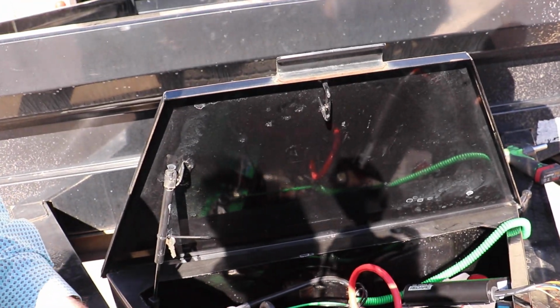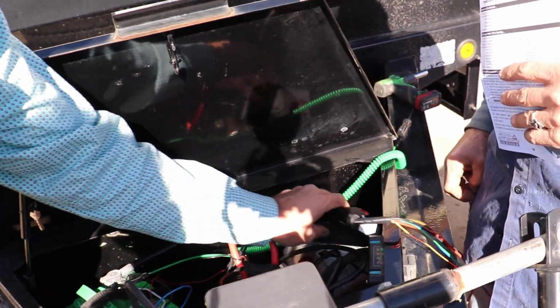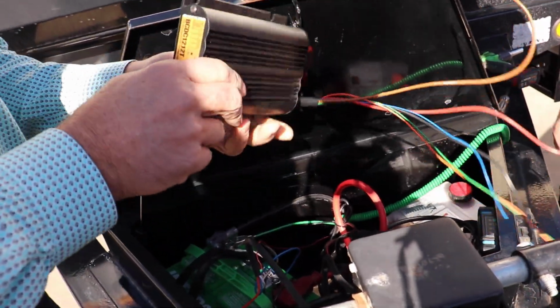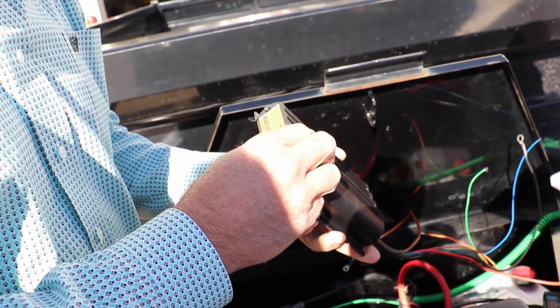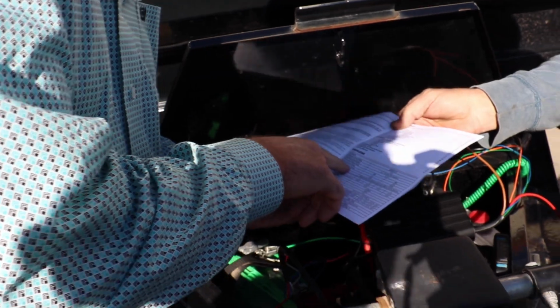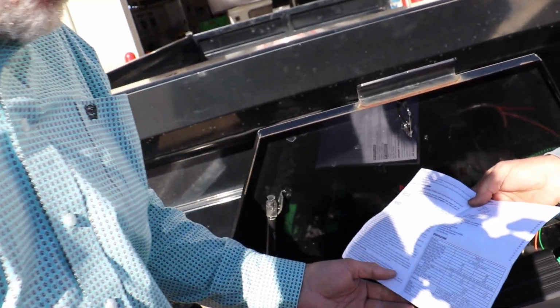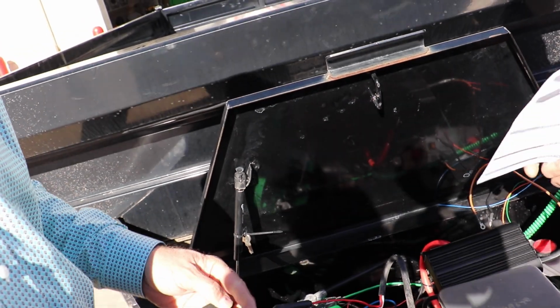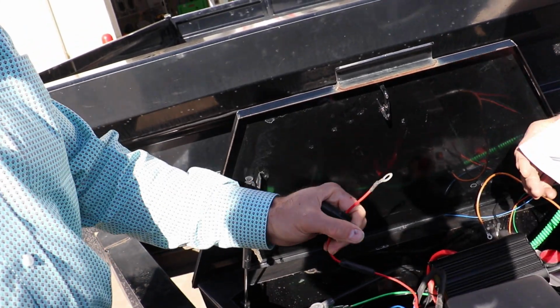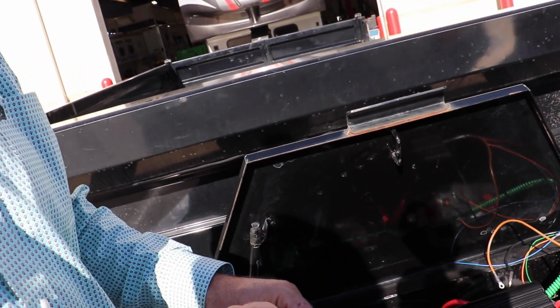It's a 20 amp circuit. I wonder if this can live on a 20 amp circuit. It's got a table in there for fuses. Output is 11 amps, anywhere from 15 to 23. So we can just use this. Just hook it right to that. It's in their range, so. And use that fuse there.